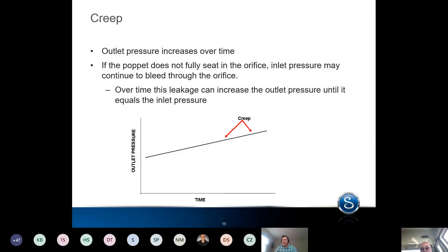Now, another aspect of regulator behavior, or I guess some of the regulator issues you can see, is creep. And this is the most common issue I've seen in the field. Creep is the rise in outlet pressure when there's no flow.